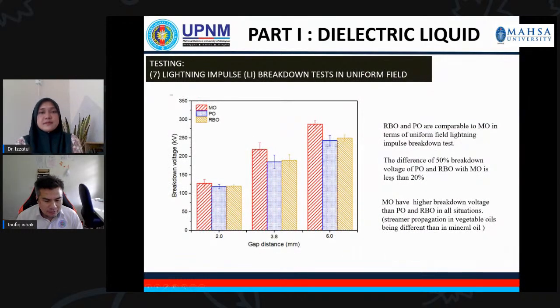Right, this is the result that we obtained during the testing. It's quite interesting. Based on the result, we can see all the oils at different gap distances, compared to the AC gap distance, which is normally 2.5 mm. For lightning impulse, we can increase the voltage between 3.8 and 6.0 mm gap distance.